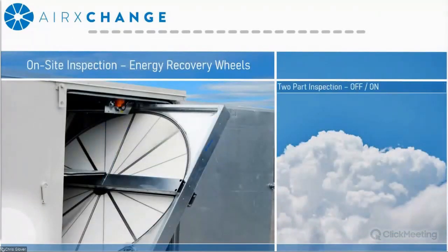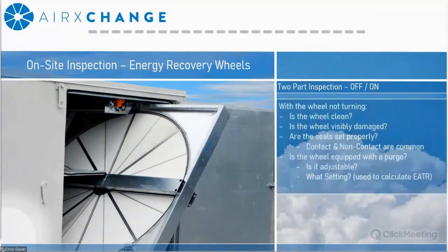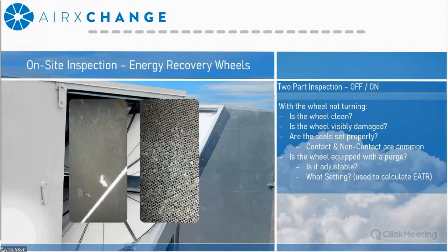All right, so once the general system has been inspected, you're going to want to inspect the actual energy recovery component itself to see if it's operating properly. Starting with an energy recovery wheel, it's a two-part inspection, one where the unit is on and one where the unit is off. Starting with the unit off, what you're going to look for is, is the wheel clean? It's usually pretty apparent. Here are a couple examples of some dirty wheels.